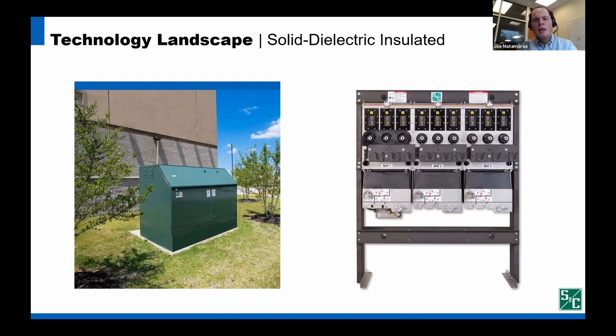On the supplier push, suppliers were able to extend molding technologies beyond molding arresters and fuses and separable connectors to molding vacuum interrupters inside solid dielectric switchgear. There's also been advancements in overhead reclosers and interrupters, in terms of reduced size and use of vacuum interrupters, and elimination of oil in those overhead reclosing applications through molding in vacuum interrupters. Some of this vacuum interrupter and recloser technology has then been applied in underground. That said, a dead tank fault interrupter underground application is quite different versus an overhead recloser application at line potential. But with that, let's review the advantages and challenges to solid dielectric technology.